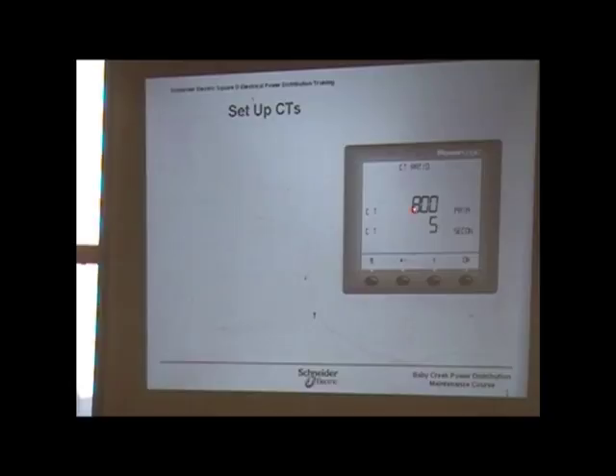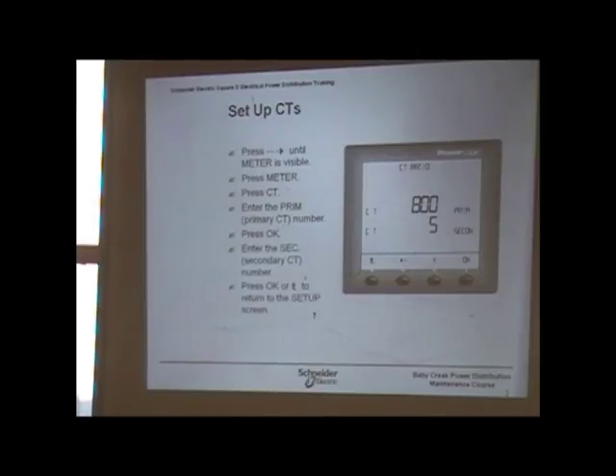And then it'll flash actually one number at a time. So let's say the first digit starts to flash, and if it's 1,000 to 1 or 500 to 1, you bring it up to 500, and then you hit OK, and then the next digit will start to flash, and so forth. Once you hit them all and hit OK, it'll come back and start on the secondary. Then you hit OK again. So you've actually gone through each individual digit, hit OK, and now you're going to back up. Like I said, go into the meter, then CTs, enter the primary CT number, press OK, the secondary CT number, press OK, press OK to return to the setup screen, and then press again to get out or to save the changes.